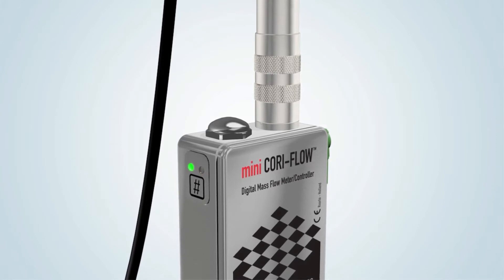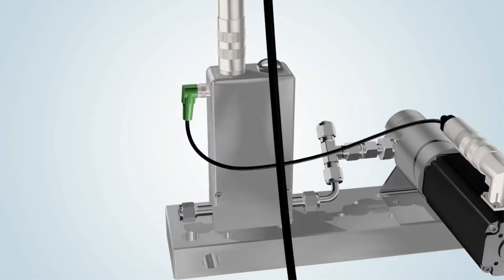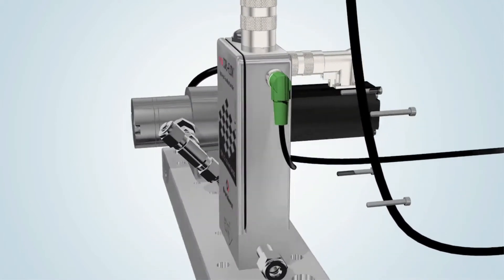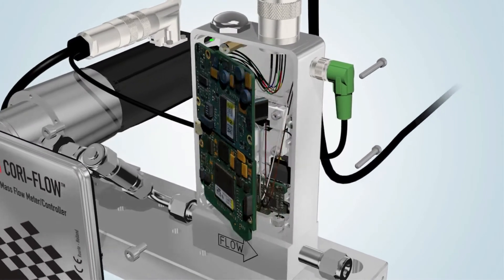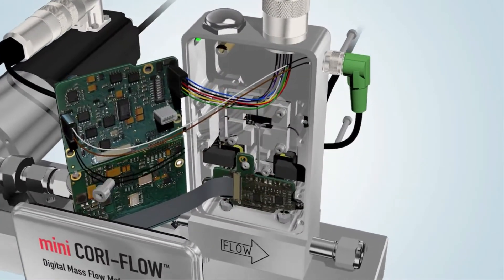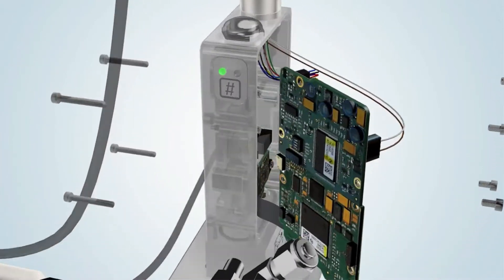Inside the robust mini Cori flow housing are the digital electronics, optical sensor, and sensor tube. The internal diameter of the sensor ranges from 0.25 millimeters to 3.1 millimeters. Once the power source is connected, the sensor tube immediately begins to vibrate.